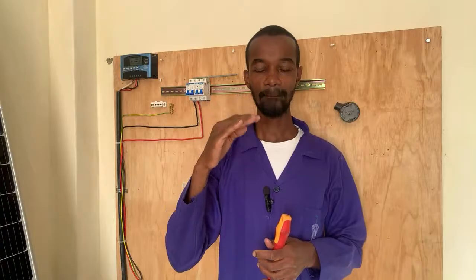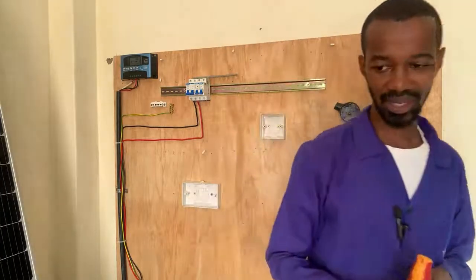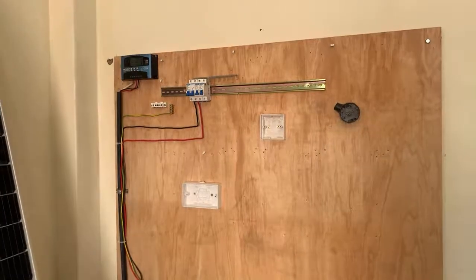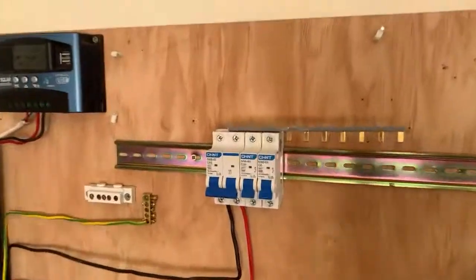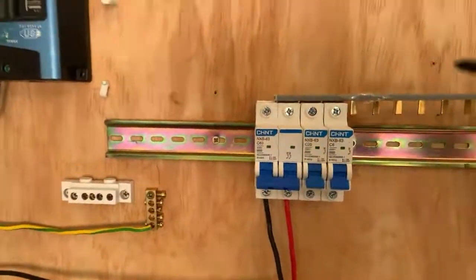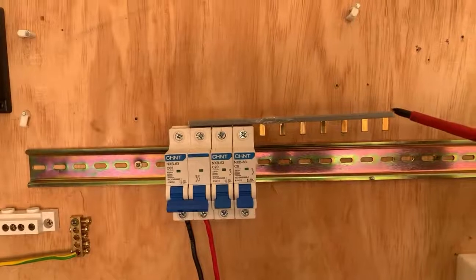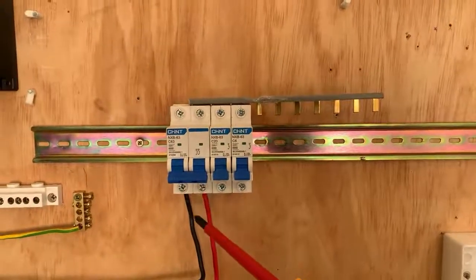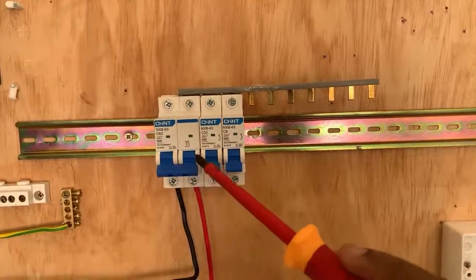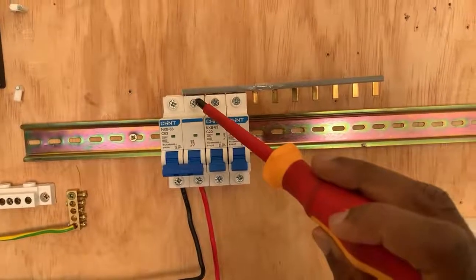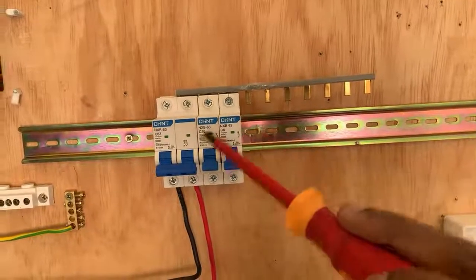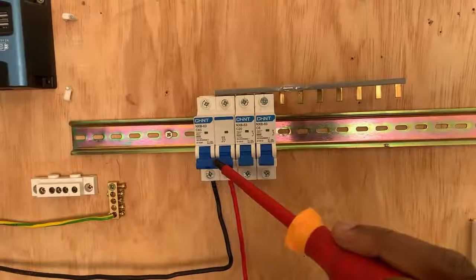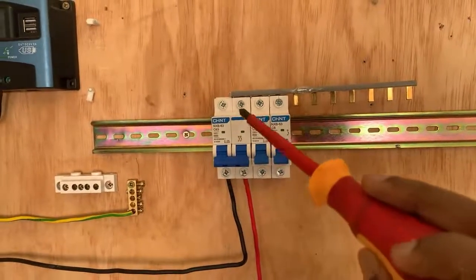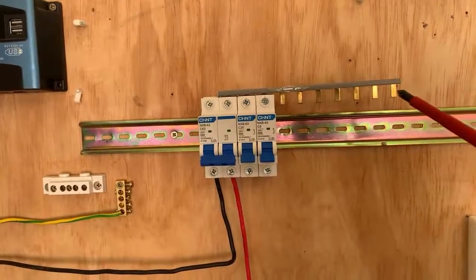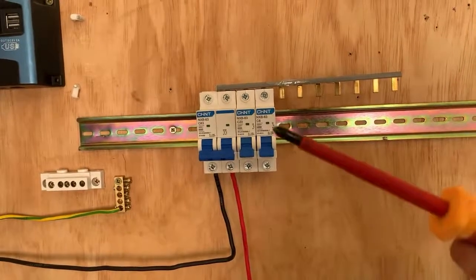Forgive me, I've not gone in order. It's supposed to be red, yellow, blue. Yes, RYB. So we have already connected our MCBs there, and just to let you know that I have made sure that I connect them using this bar, and from this particular point where we have the incoming phase, it will go all the way, and as you can see, I've connected there, and then I've linked this MCB so that once this DP MCB is on, then it means that this phase current will flow all the way up to this particular point for any connections that we may be having.